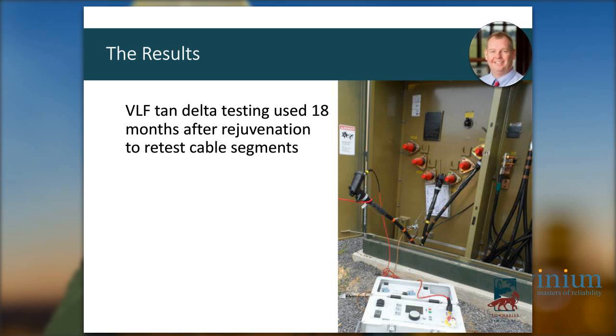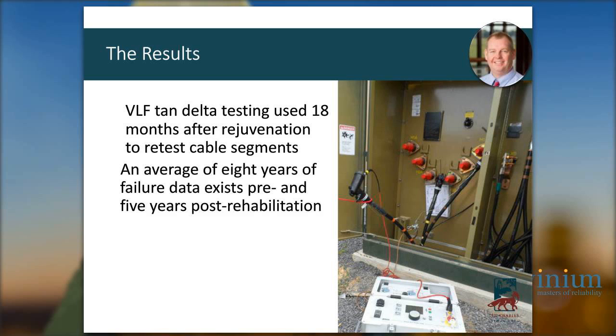What we had to understand is that it's not a miracle fluid. It's injected down the strands through the center of the cable, and it permeates through the insulation to fill the trees and voids, but it doesn't happen immediately—it takes time for the fluid to permeate through the insulation. That's why at 6 months, on some spans, it just hasn't yet filled all the trees it needs to fill to restore the insulation.